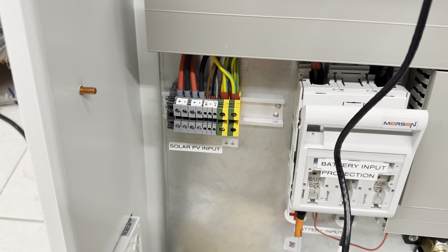Down there we have the solar PV input protection, surge protection, DC isolator and fuses. And this is where you connect your solar panels. This inverter has a single MPPT, but you can still parallel two strings with maximum current up to 27 amps. The maximum PV input is 6 kilowatts, and the voltage can fluctuate between 120 and up to 450. I advise you to connect a minimum 8 panels for this inverter. If you want to have a healthy system, you need definitely minimum of 8 panels.